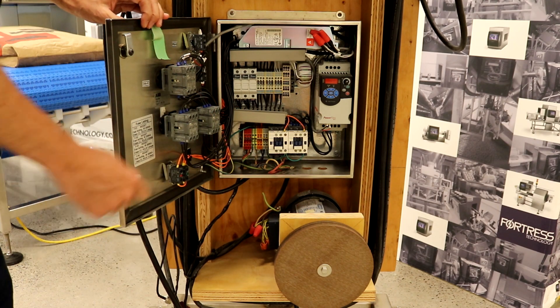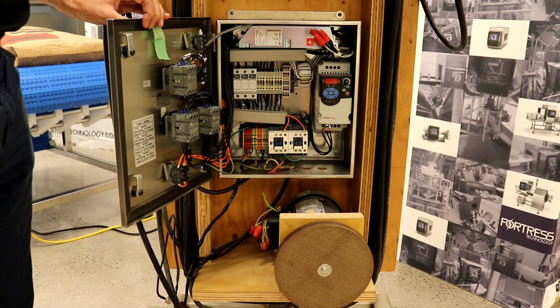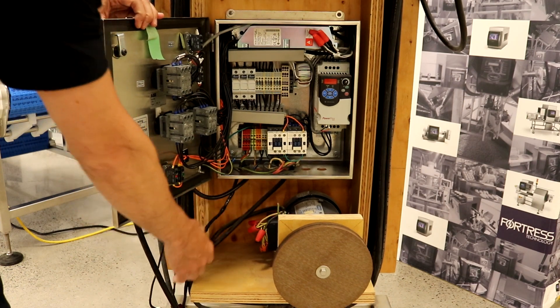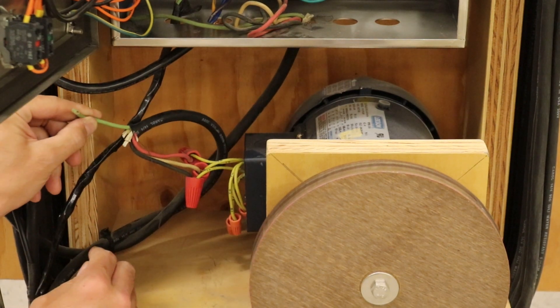Inside the control box is the VFD, which is connected to power through an RFI or EMI line filter which prevents noise from transmitting through and from the incoming power bus. The cable to the motor in this case is the weak point of the setup. VFD cabling is not utilized, so there is no shield on the cable and it can radiate EMI.